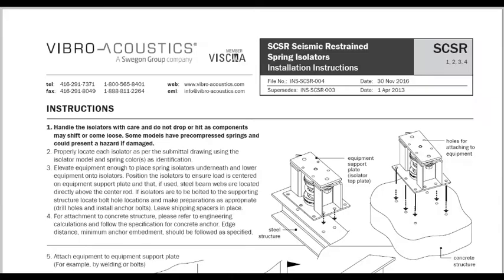After a warning about proper handling of the isolators, the next instruction on the installation instructions page says to properly locate each isolator using the model and spring colors as identification. The instructions then go on to explain the process for installing the isolators and then the equipment onto those isolators. We won't cover that part in detail here, however, there is one instruction here that is important with cooling towers, and that is to center the isolator under the equipment load or under the web of a cooling tower base, which we'll cover in another video.